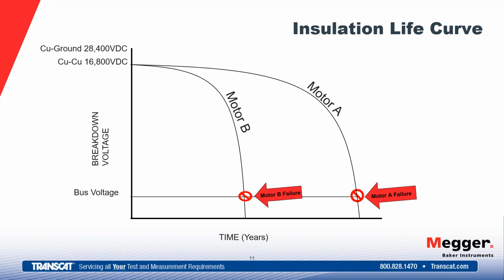The difference between motor A and motor B in this scenario here may be its environment, how it's treated, lots of starts and stops. Does it have voltage imbalance? Is it being overloaded? Is it living in a really dirty environment? It's a coal power plant, has a lot of coal dust on it, or a cement plant, cement dust, chemical plants with a lot of corrosive gases that can erode that insulation. What environment is it living in? That's the difference here between motor A and motor B.